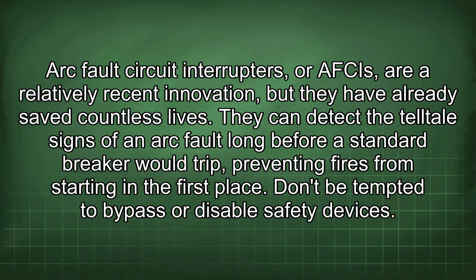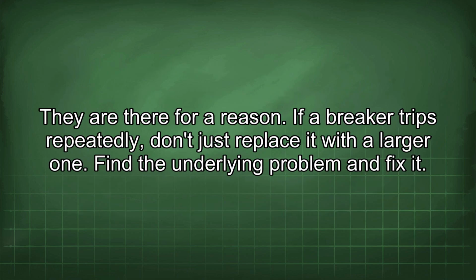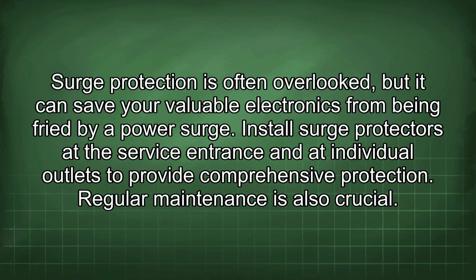Don't be tempted to bypass or disable safety devices. They are there for a reason. If a breaker trips repeatedly, don't just replace it with a larger one. Find the underlying problem and fix it. Surge protection is often overlooked, but it can save your valuable electronics from being fried by a power surge. Install surge protectors at the service entrance and at individual outlets to provide comprehensive protection.